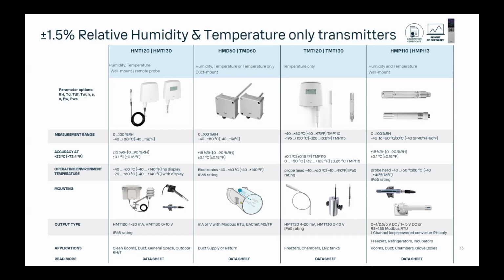And then right there in the middle is a newer offering for us, a temperature only probe with the TMP 115. You'll see it in the thermal well at the bottom. That's designed mainly for freezers, chambers, and liquid nitrogen tanks. So that can go down all the way to minus 80, minus 200 with the TMP 115. Some of them are only calibrated down to minus 90.